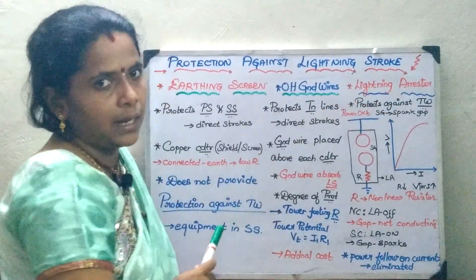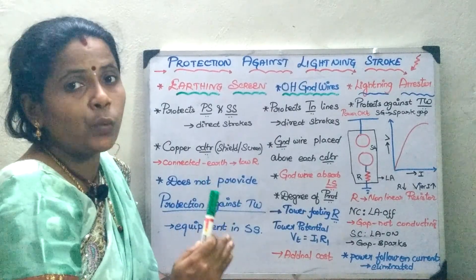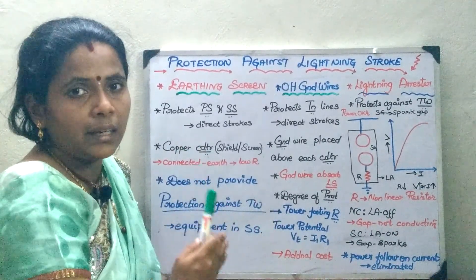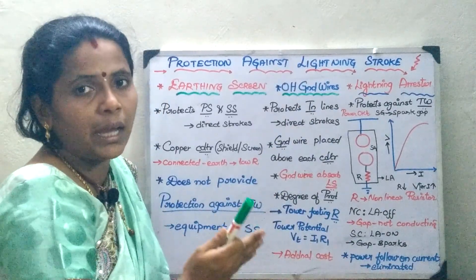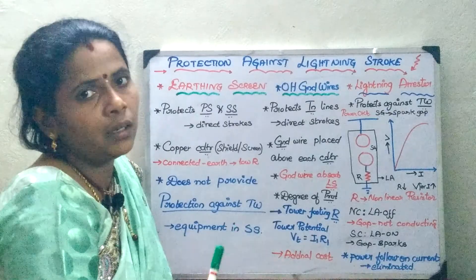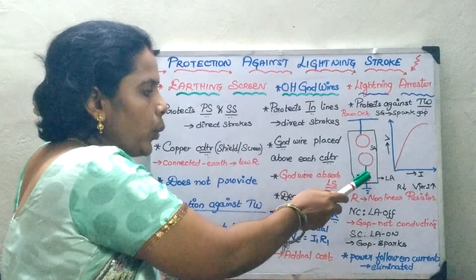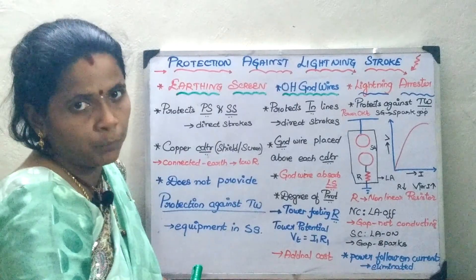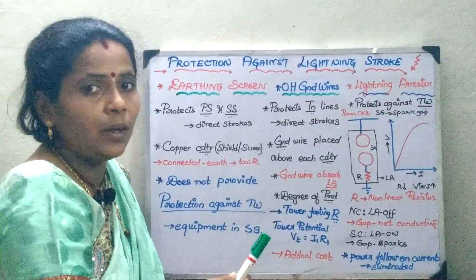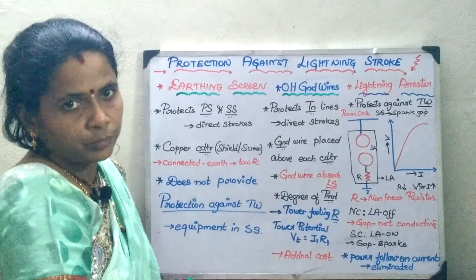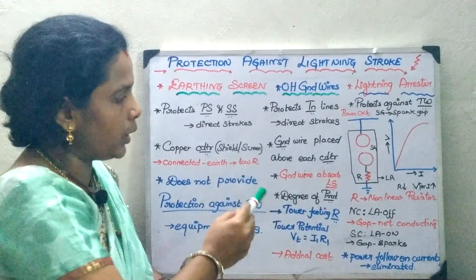Now we will see about the lightning arrester. The drawback we have seen in the previous two types is that they are not able to give protection against travelling waves or surges, which creates a harmful effect and damages your equipment. The lightning arrester bypasses this very high lightning discharge to the ground. The equipment consists of two components: one is your spark gap and you have a non-linear resistor setup. On one hand it is connected to the power circuitry to be protected, and on the other side it is grounded.